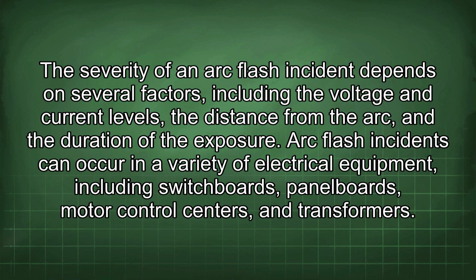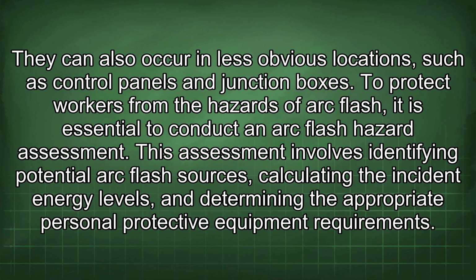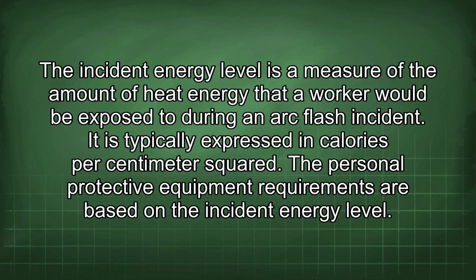Arc flash incidents can occur in a variety of electrical equipment, including switchboards, panel boards, motor control centers, and transformers. They can also occur in less obvious locations, such as control panels and junction boxes. To protect workers from the hazards of arc flash, it is essential to conduct an arc flash hazard assessment. This assessment involves identifying potential arc flash sources, calculating the incident energy levels, and determining the appropriate personal protective equipment requirements. The incident energy level is a measure of the amount of heat energy that a worker would be exposed to during an arc flash incident. It is typically expressed in calories per centimeter squared.